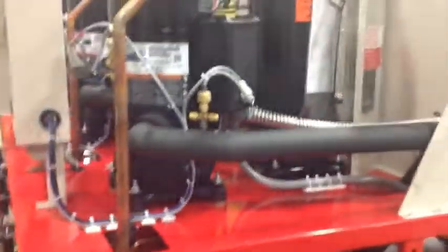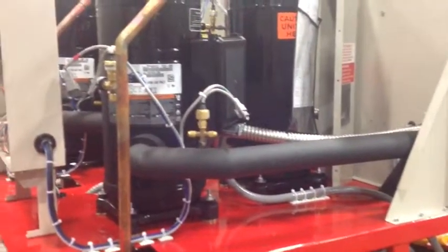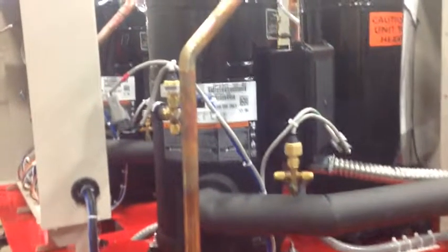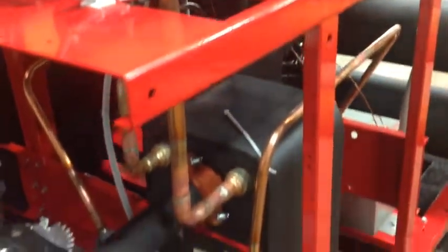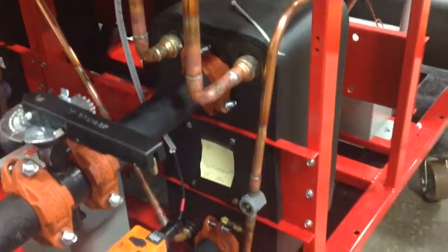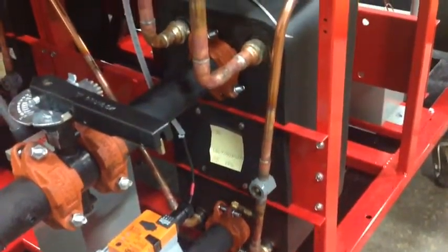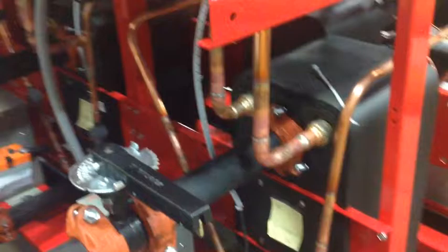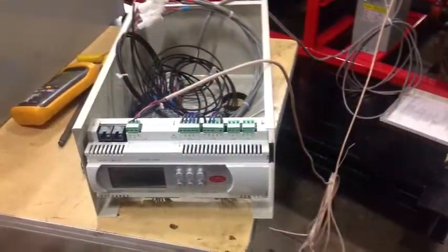Now we'll see some of the key refrigeration components. In front of us first here, the low pressure transducer, and then moving around to the high pressure transducer and high pressure switch. You can see the gray button just on the left edge for the manual reset of the high pressure switch. You'll note that there are 4 refrigerant connections and 2 water connections. That's because each condenser and evaporator is dual circuited on the refrigerant side.